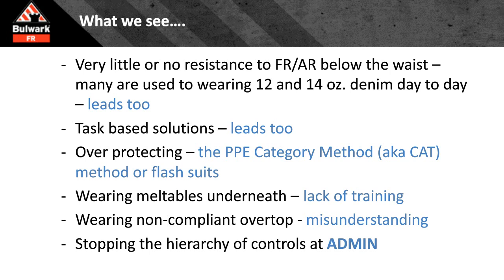What you wear underneath has to be, at a bare minimum, natural fibers. Are we coaching that all the way through the process, or is there an opportunity, due to lack of training or forgotten training, to introduce meltables? Could we be wearing non-compliant garments over the top? For example, we go to the tool room and grab a high-vis vest. Are all the vests in the tool room flame-resistant and arc-rated to our hazards? Do we have non-FR vests in there, or vests not tested to the hazard? Do we stop the hierarchy of controls at admin and not drill all the way down to PPE?